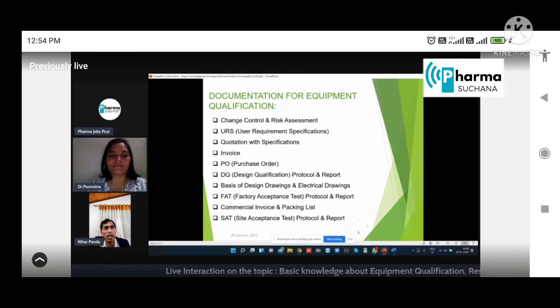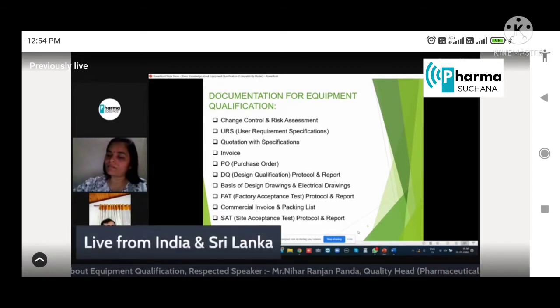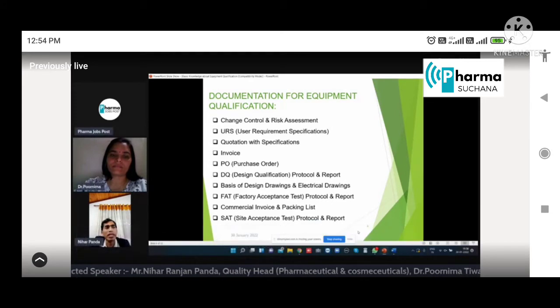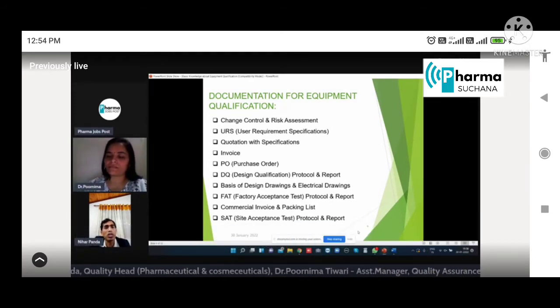Those documents are like change control. Whenever you are going for a new equipment or modification of equipment or transfer of equipment or relocation of equipment, for that you need a change control. Along with the change control, you should do the risk assessment. What is risk assessment? This is related to RPN number calculation or failure mode and effects analysis, like that.